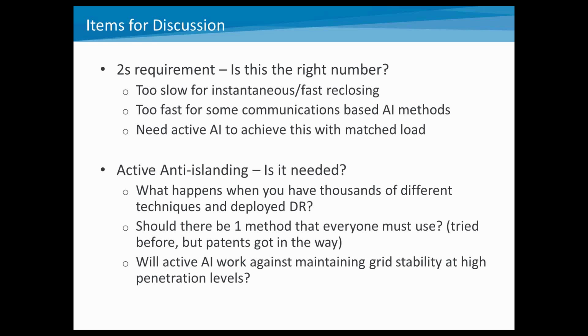Bullet point two there, should there be one single method that everyone must use? Well, in the active anti-islanding world, we actually tried this, before everybody started patenting all their anti-islanding techniques. Now there's probably 20 different patented anti-islanding techniques out there, and it's probably too late to get that genie back in the bottle. But there may be other permissive ways to have a single method everyone must use.